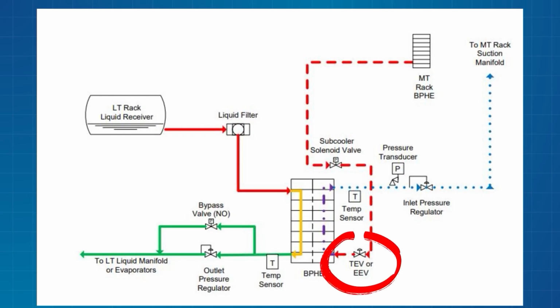Okay? Anytime my EMS system shuts off my subcooler, it's gonna open that bypass. Now, you just heard what I said, EMS system. Not my little subcool control from Sporlan. All right, we can still have that same phenomena happen where my temperature on this leaving line gets lower than the set point on this, and we turn off this solenoid, we open this solenoid, and this guy goes to 100%. It's still gonna happen.